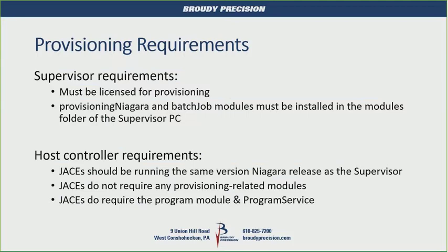The JACE doesn't need any of the provisioning modules. It's just the supervisor that requires those. They do require the program module and the program service, which are standard modules that you have in there already.